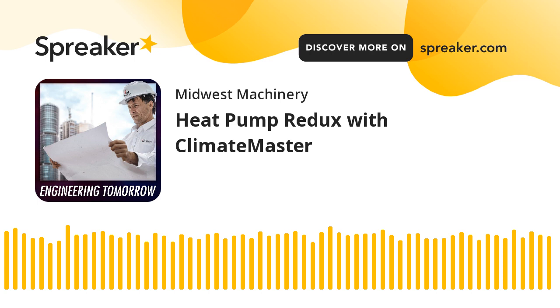So we need to put this heat somewhere. So what's happening is the cooling tower on the system is running and it's rejecting that heat. The boiler is off. I have too much heat. I do not need any more heat. The boiler is not running. So in the summer months, like I mentioned, the only thing that we're going to be needing to run is your cooling tower and your pump to circulate the water.